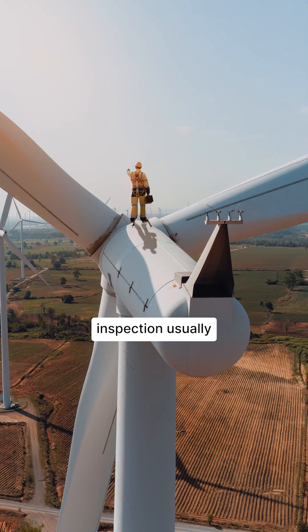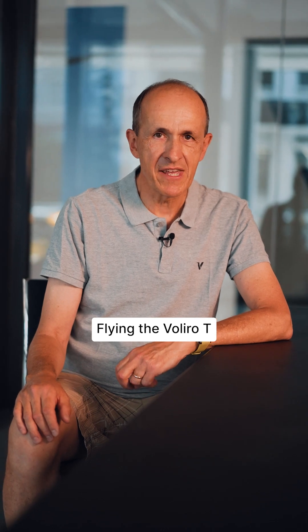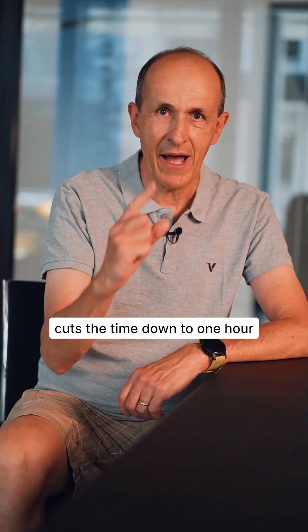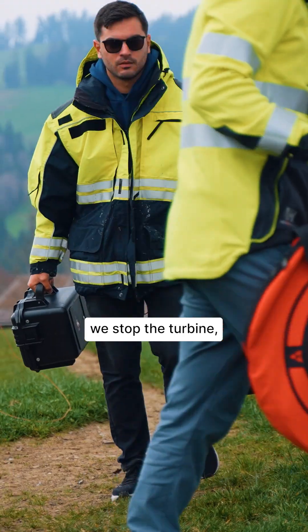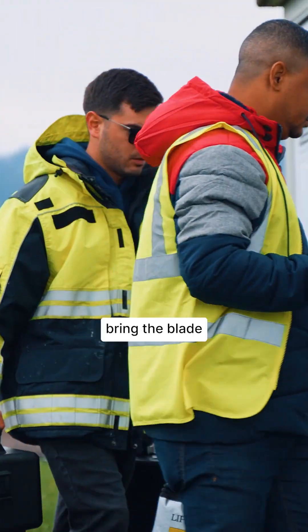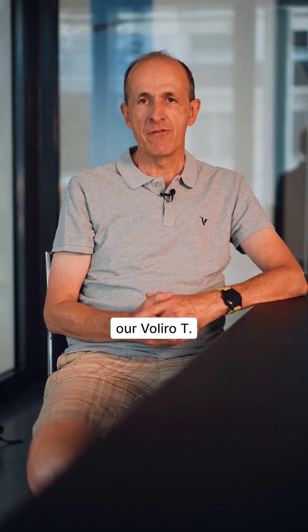Conventional LPS inspection usually takes a full day to complete. Flying the Voliro T cuts the time down to one hour only. First thing we do when we arrive on site at the turbine, we stop the turbine, bring the blade into position and then start setting up our Voliro T.